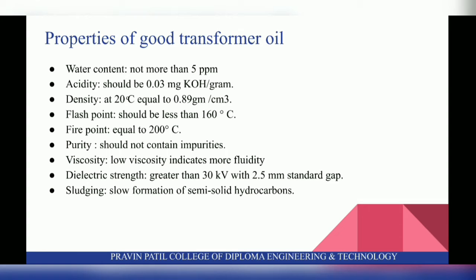Next is dielectric strength. The dielectric strength of oil should be greater than 30 kV with 2.5 mm standard gap. The presence of moisture reduces the dielectric strength. The oil should be filtered periodically and transformer oil should be conditioned.